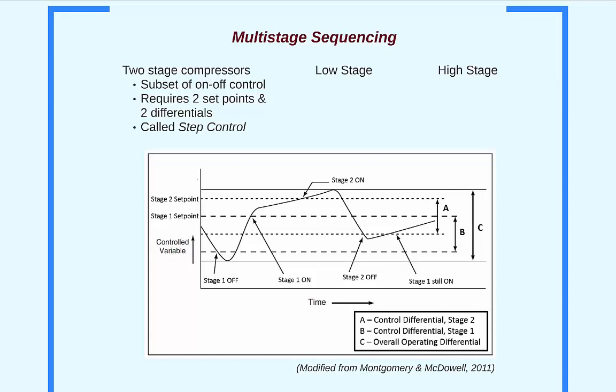Let's look at the example of a two-stage DX unit designed to supply 55-degree air. The low stage set point is 55 degrees with a differential of 2 degrees, meaning the low stage will turn off when discharge air is equal to 53 degrees. The high stage set point is 57 degrees with a differential of 3 degrees, meaning the high stage will turn off when discharge air is equal to 54 degrees.